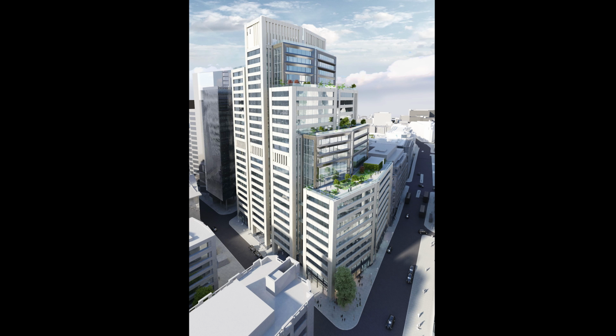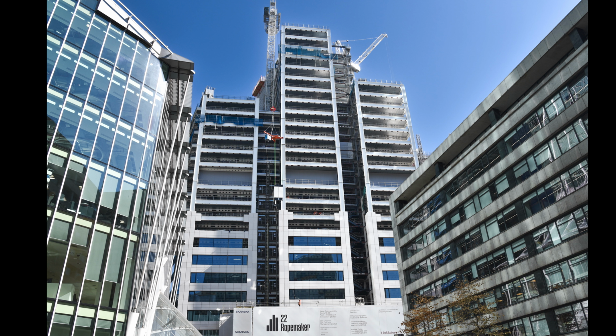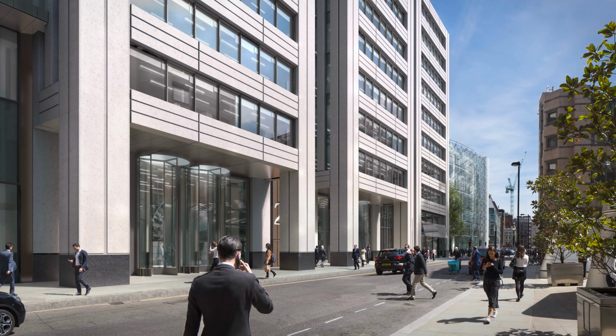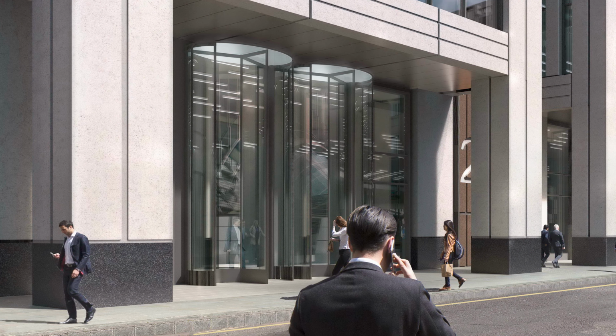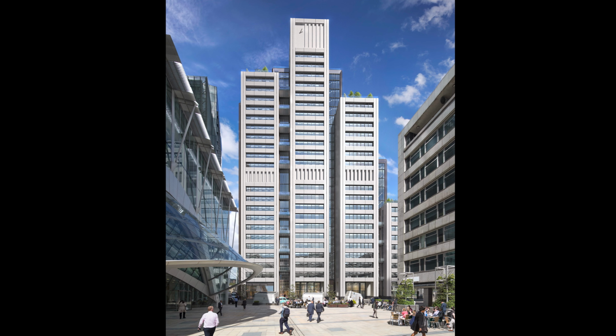I'm Julia Mackey. I'm a technical consultant at Hilson Moran, and my main responsibility is performing CFD simulations for both the internal and external built environment. I've worked on the Ropemaker building in London, and I've used CFD simulation to assess the interface between the external and internal environments. In particular, this was relating to revolving doors, and the client was concerned that in the winter, particularly where there's heavy footfall, how are we going to predict the amount of cold air that could be coming in and potentially interfering with the heating design.